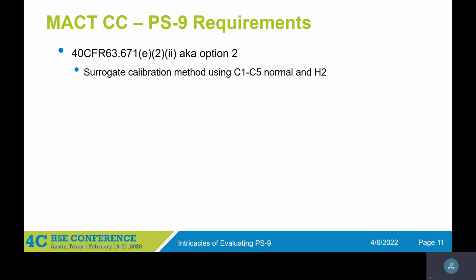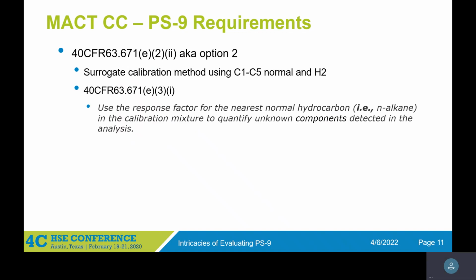So now looking at how MACT CC shifts and changes those PS9 requirements. MACT CC gives you 2 options for the cylinder gases that you need to use. You either have the surrogate calibration, which is going to be the C1 through C5 normal, so your methane, ethane, propane, butane, pentane, and hydrogen as an option. If you go with this option, it is specified to use the response factor for the nearest normal hydrocarbon when calculating and detecting unknowns in the analysis.